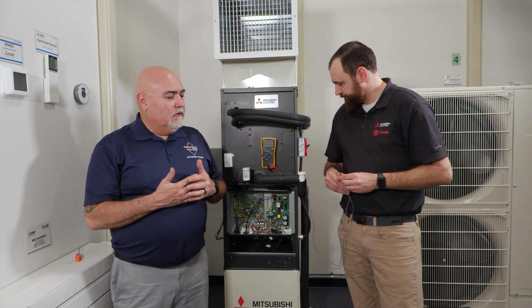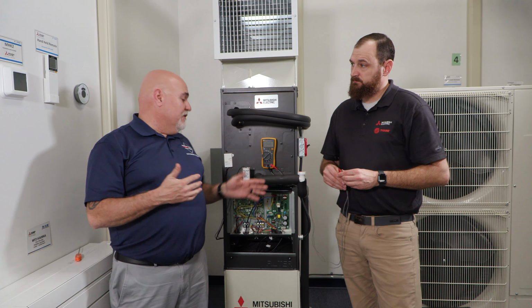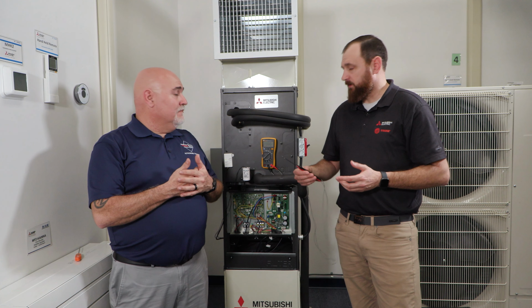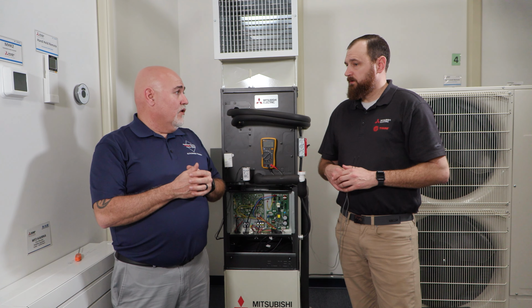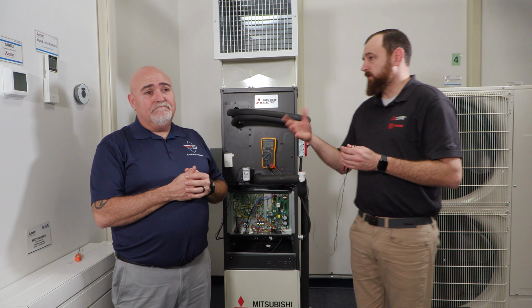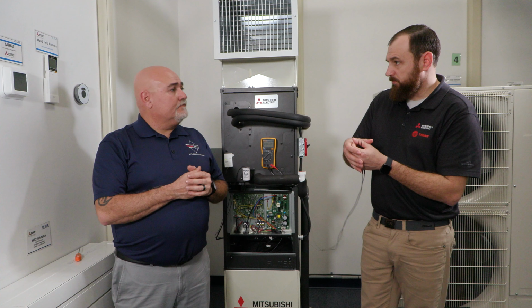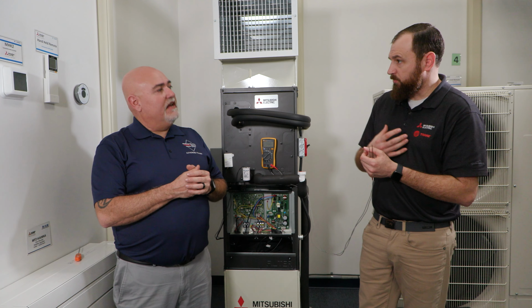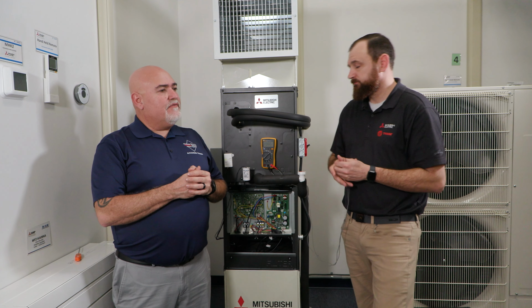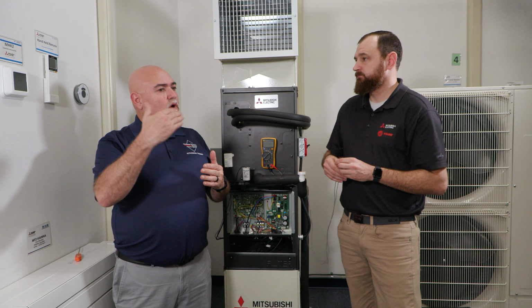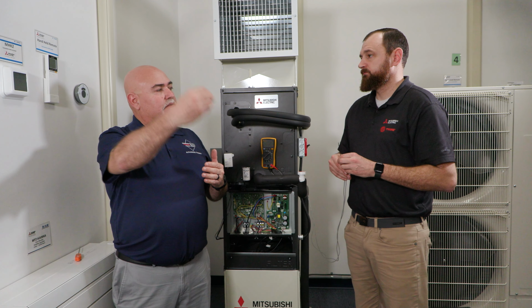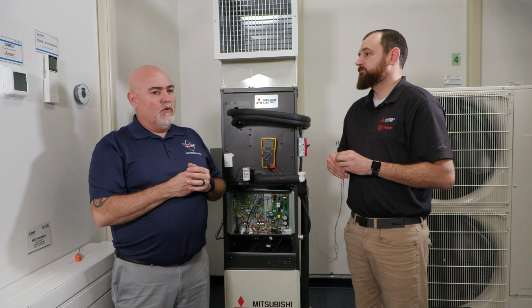Right? Okay. So now if the motor is not putting out rotational feedback, and we're going to talk about these voltages in a minute, then the motor is defective. And the indoor board is good, because we're assuming the indoor board's not getting that signal back. Exactly. Every time that motor makes one revolution, it sends 15 volts to the indoor board.